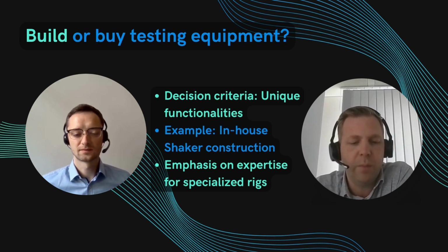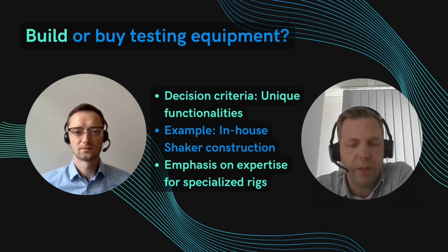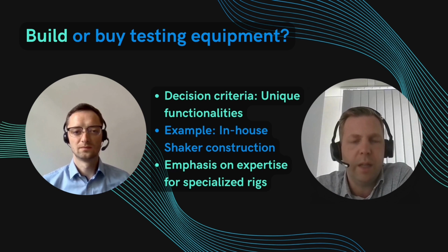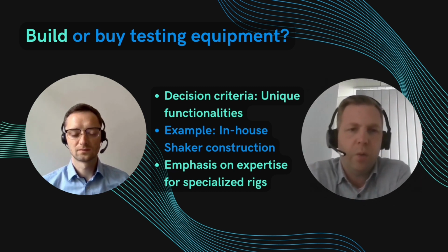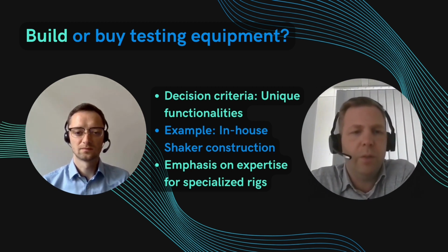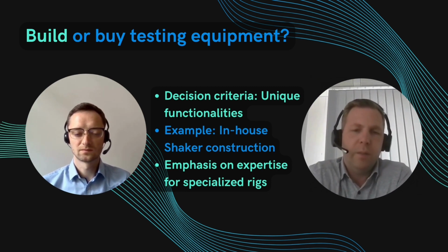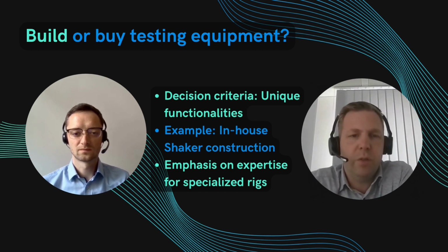Our developers must grasp how your component responds to influences and if it has been developed correctly, properly designed. So we already have several special test benches in use, especially in the component also cell swelling behavior, recording of forces during the electrical charging and discharging of cells. These things are already significant, and we observe that our initially more or less standard battery testers are also progressively becoming more specialized. So there are extensions, there is special measurement tech, and now we have the topic of new cooling tech, where we generate cooling circuits. This is definitely not something you can purchase off the shelf anymore.